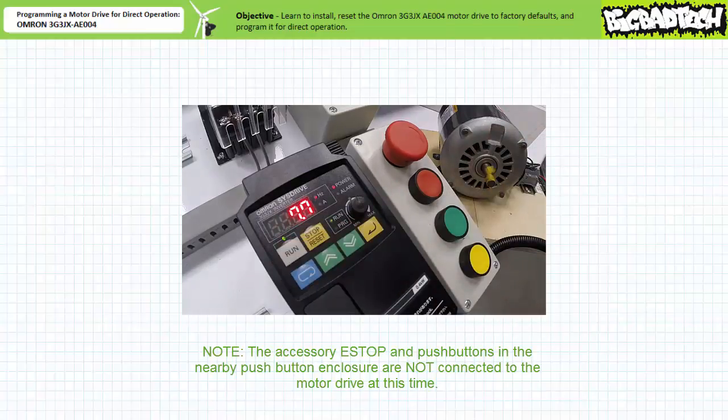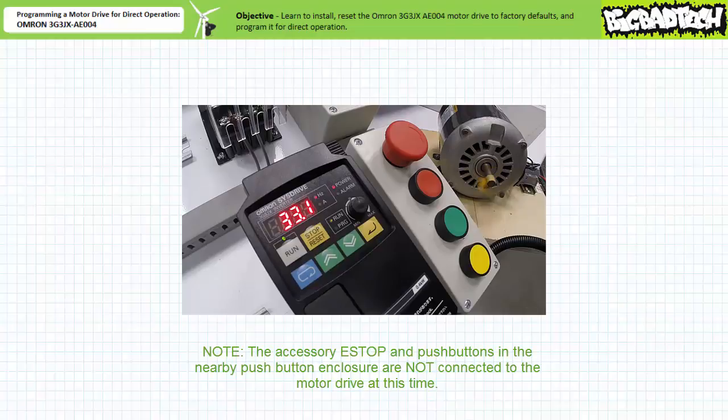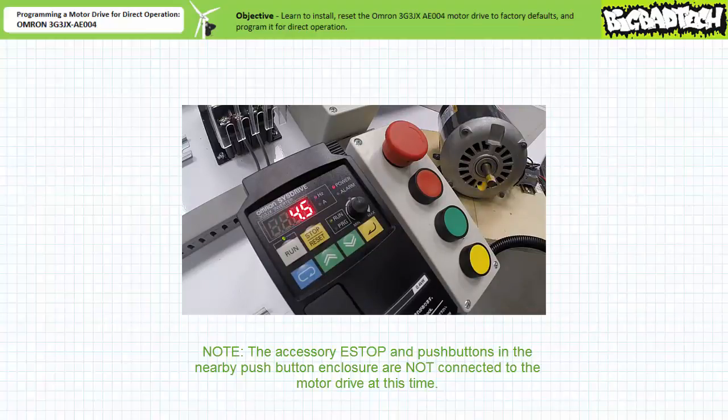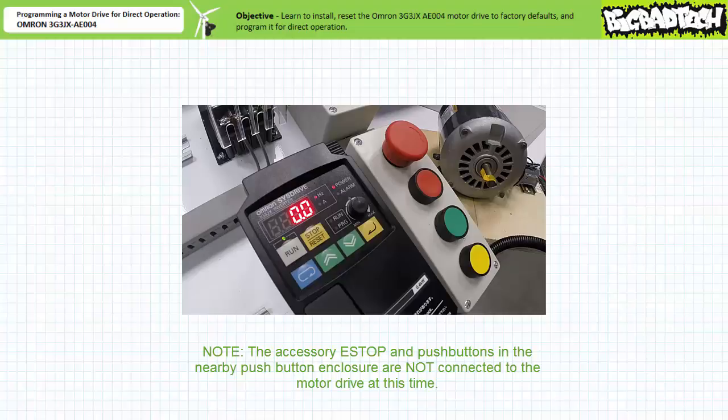When an operator presses run when the frequency adjustment knob is halfway, the motor drive increases the applied frequency to roughly 30 hertz. The motor accelerates and speed stabilizes. When an operator presses stop, the motor decelerates and turns off. Note the run LED turns off after the control deceleration period has ended.